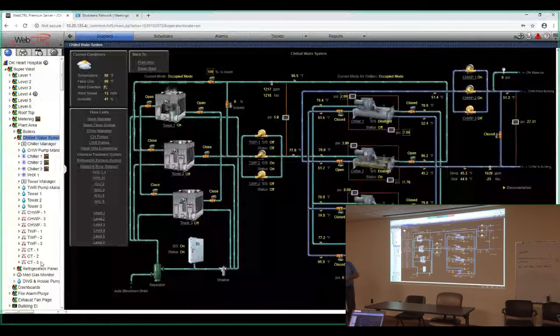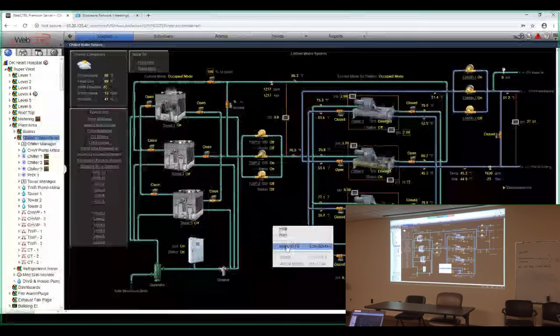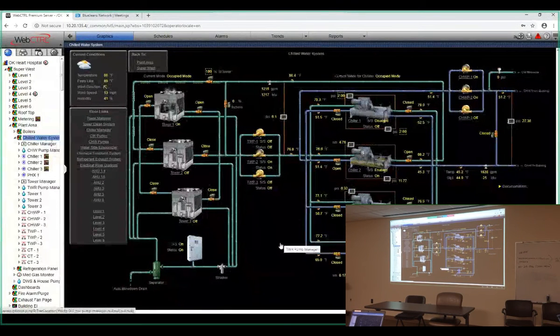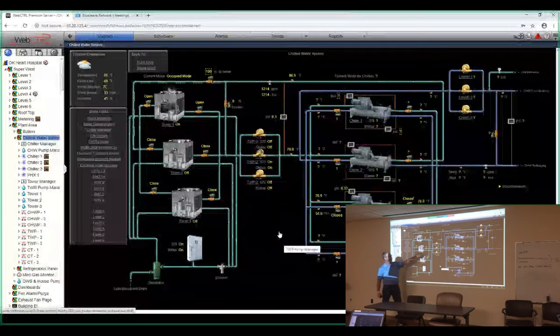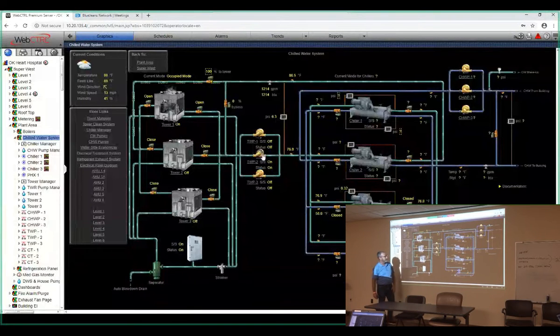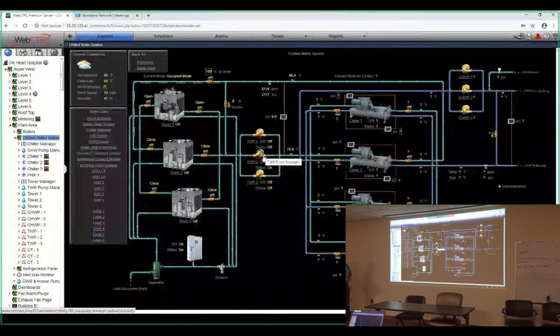Okay. So this top graphic, I tried to give you a way to look at the entire plant in one view. So you can see what pieces of equipment are running, which tower, which chiller, which pumps, and how many you have staged up. So it's just an overview. There is some detail to these graphics, but not a lot of detail. You don't see your pump speeds. You just see the status and if I'm calling for it to run or if the system's calling for it to run. So we're calling for tower pump 2 to run. It's running, it's got a status. Any questions about this graphic?